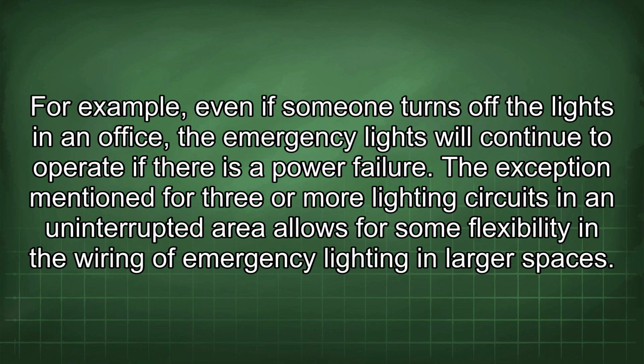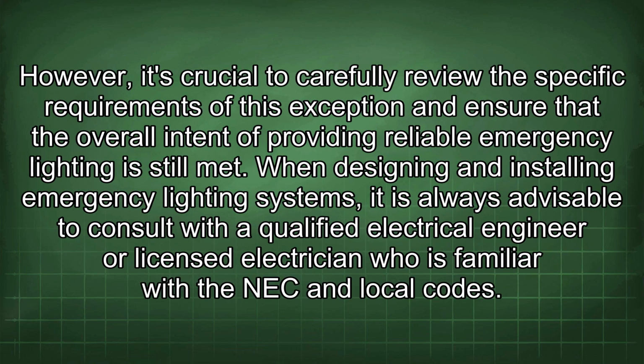The exception mentioned for three or more lighting circuits in an uninterrupted area allows for some flexibility in the wiring of emergency lighting in larger spaces. However, it's crucial to carefully review the specific requirements of this exception and ensure that the overall intent of providing reliable emergency lighting is still met.